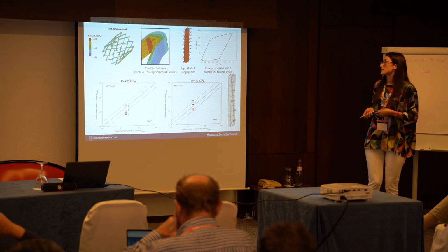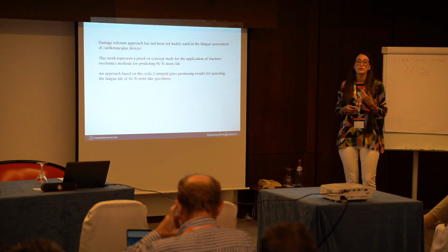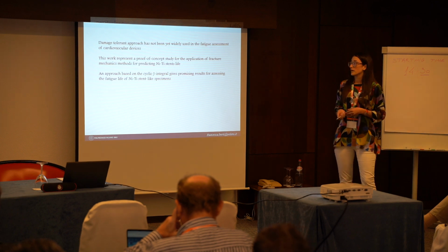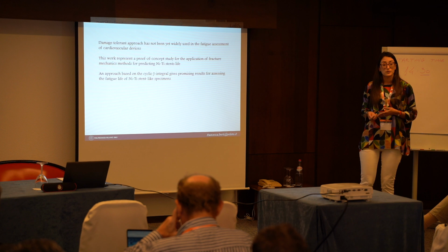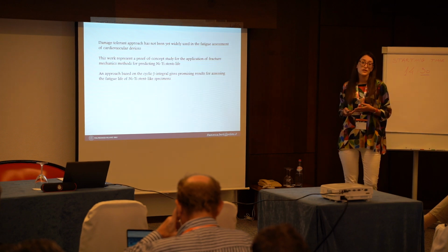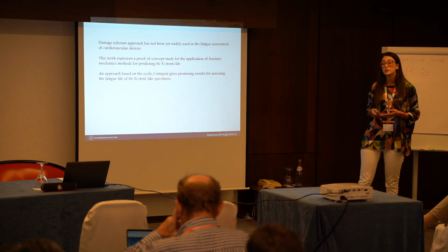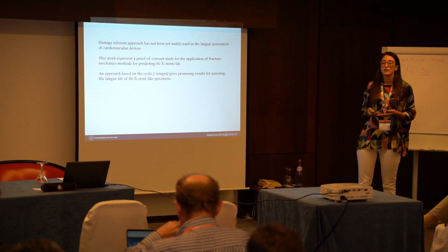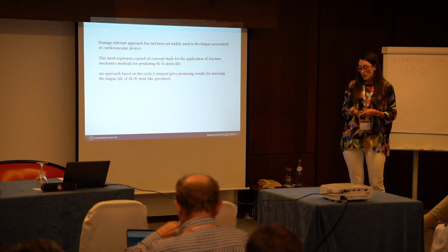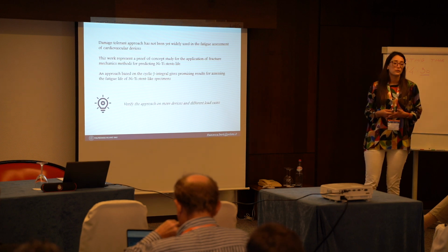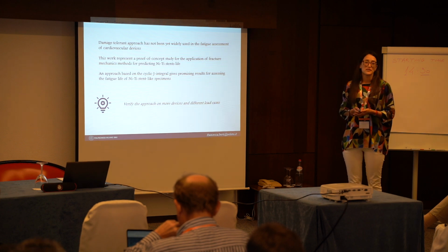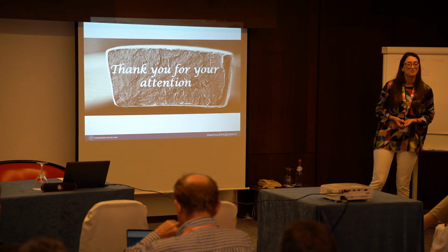So we know that this is a preliminary study, but you have to know that the damage tolerant approach has not been widely used in the fatigue assessment of cardiovascular devices. So this is our first attempt, but our results show that the use of the cyclic J integral gives promising results. We know that we have to work more to verify this on more devices and more loading conditions, but for now that's it. Thank you very much.